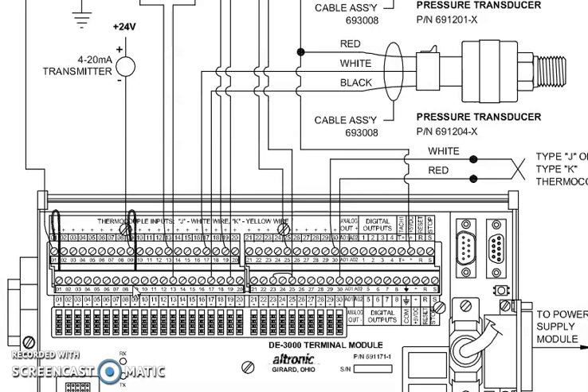So now let's talk about a little bit of Ohm's law for a moment. Ohm's law is Ohm's law, and that's why it's called law. But let me give you an example. 4 to 20 milliamps. If we take 0.004 amps and we multiply it by 200 ohms, we're going to get 0.8 volts. Likewise, if we take 20 milliamps, 0.020, and multiply by 200 ohms, we're going to get 4 volts. So actually what we do, and this is true in any industrial product out on the market that measures 4 to 20 milliamp currents, they all convert it to voltage at the end of the day.